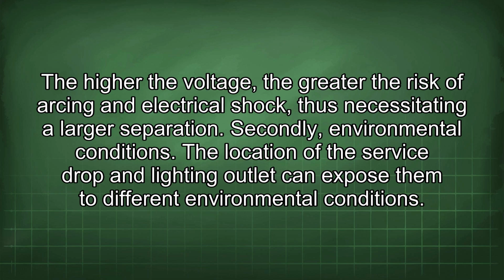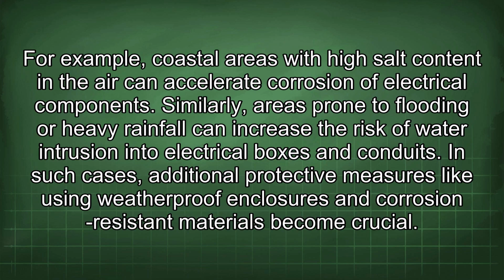Secondly, environmental conditions. The location of the service drop and lighting outlet can expose them to different environmental conditions. For example, coastal areas with high salt content in the air can accelerate corrosion of electrical components. Similarly, areas prone to flooding or heavy rainfall can increase the risk of water intrusion into electrical boxes and conduits. In such cases, additional protective measures like using weatherproof enclosures and corrosion-resistant materials become crucial.